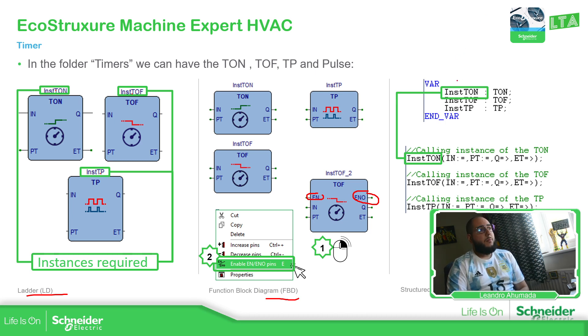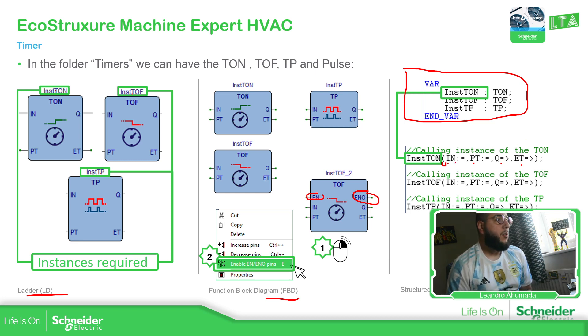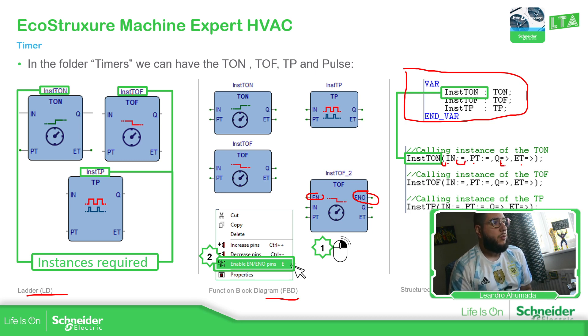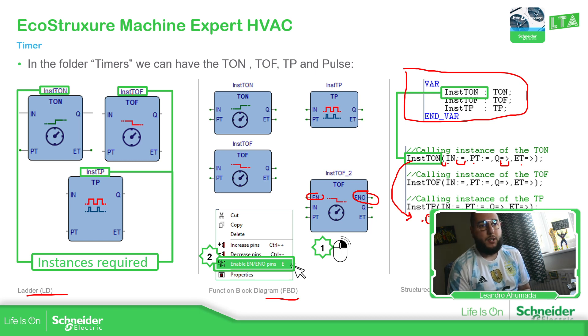For structured text it's a little bit different. What I recommend is to drag and drop into the local variables, then drag and drop that name into the code. You can type the parentheses to see all the different inputs and outputs. To define a variable into the input of the function block, use the colon and equal. For the output, use equal and then the arrow symbol. Another possibility is to use the name of the instance and then use the dot to access the output.